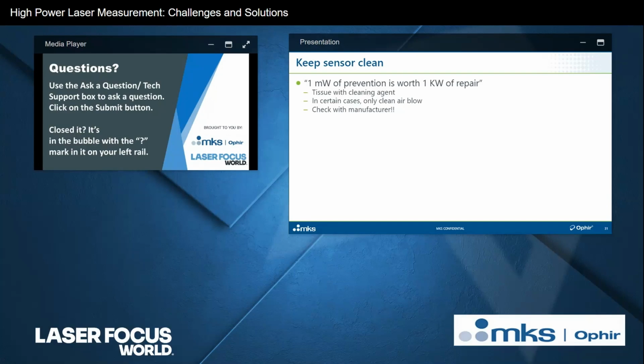In some cases, depending on the sensor type, no cleaning agent and no soft tissue or anything, just a clean air blow. Those reflective cone sensors are like that. You don't want to touch those cones because the reflective coating is somewhat delicate. Check with the manufacturer for cleaning instructions and follow them.